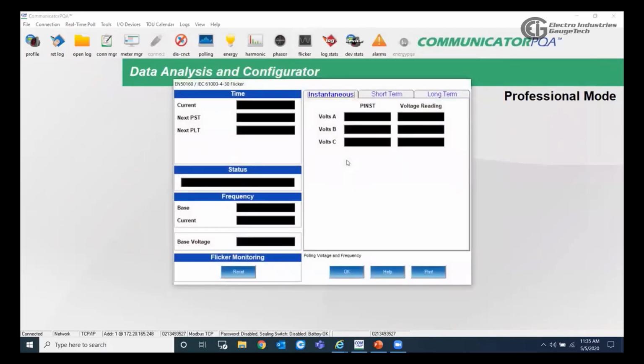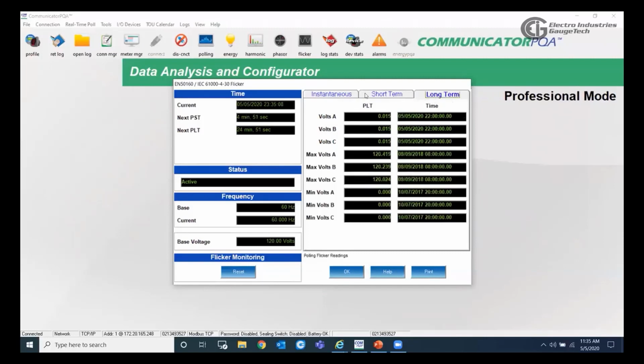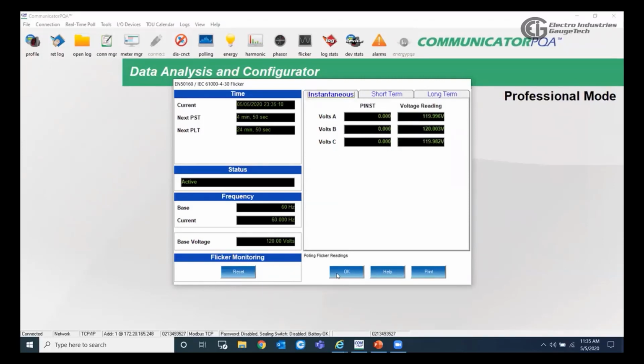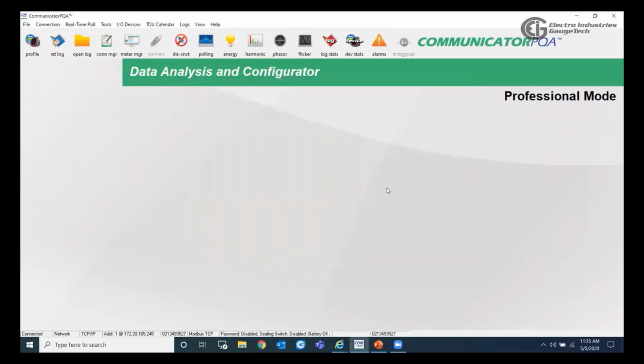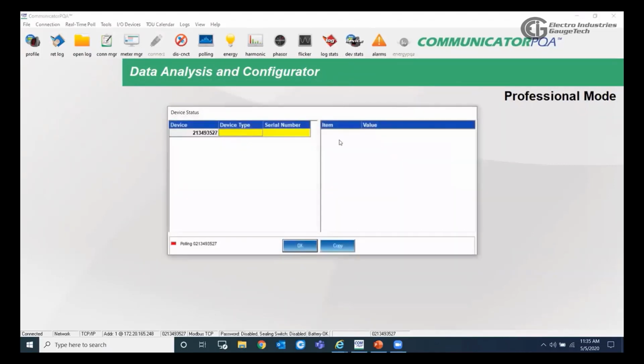The flicker: this meter has the ability to also give you the short term and the long term flicker, and you can see that from here. The device status, this is the same window we got when we connected with the meter, which is popping up. It's the same device status window.